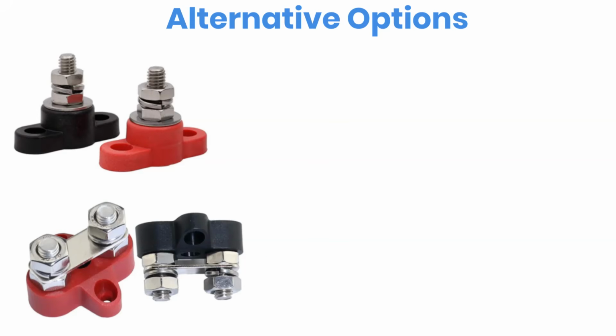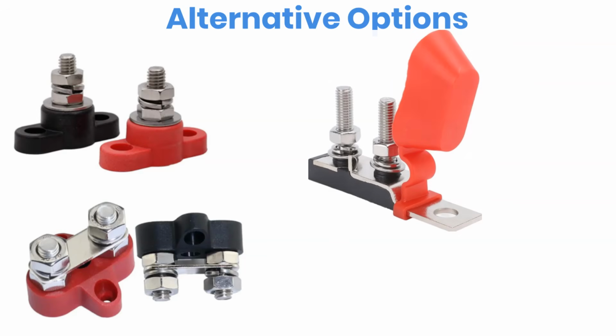Also, avoid stacking too many cable lugs on one terminal. As a general rule, no more than 3 lugs should share a single stud, and always make sure the busbar itself is rated for the maximum current your system can deliver. Another thing worth checking is the mounting hole size on your MRBF fuse blocks. Many are designed with 10mm holes, while most lithium batteries use 8mm battery studs. Some manufacturers do offer 8mm versions, so it's worth confirming compatibility before ordering your parts.